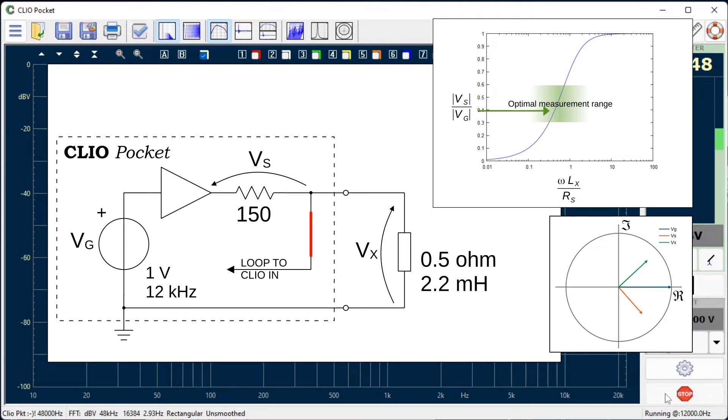Compared to the classical technique with a 1 kHz tone, in this practical case, the Clio Pocket method with sweeping tone improves the reading accuracy by one order of magnitude.